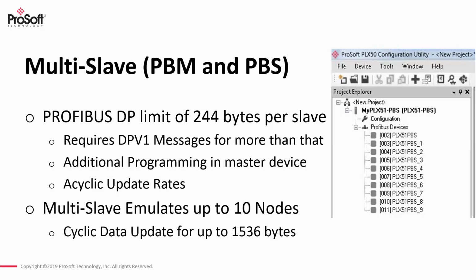when you go to configure the master, essentially you're going to pull the GSD file, which is generic station description. You're going to pull that into the master, and then you would just define multiple instances of that device because you're emulating multiple nodes.